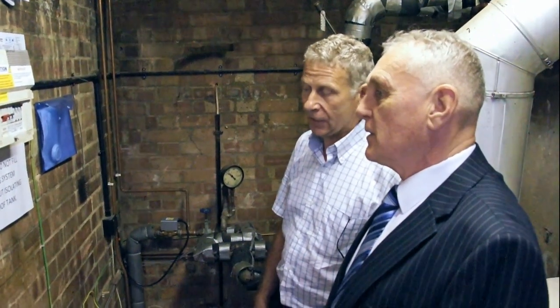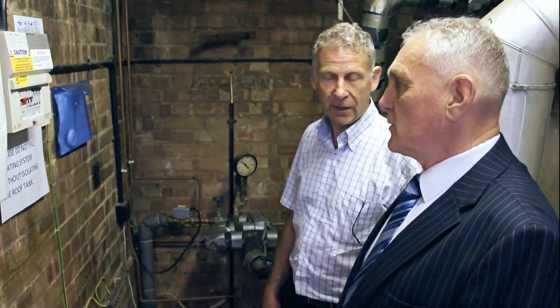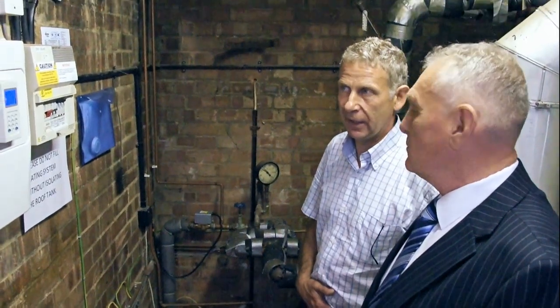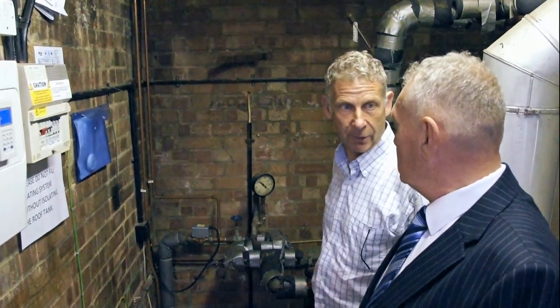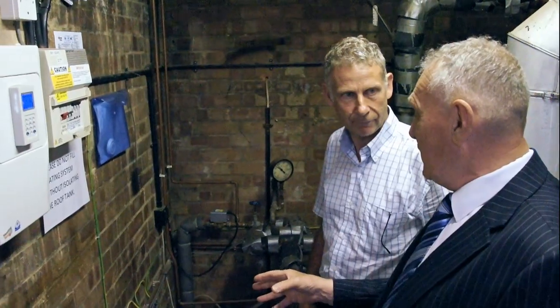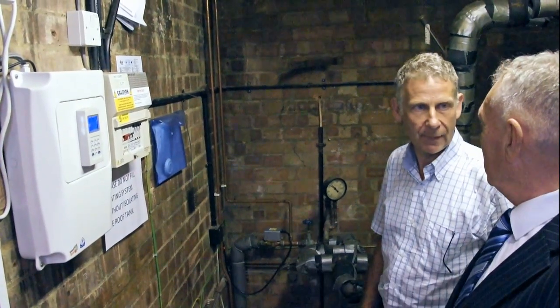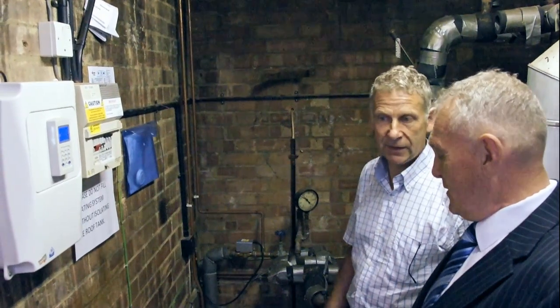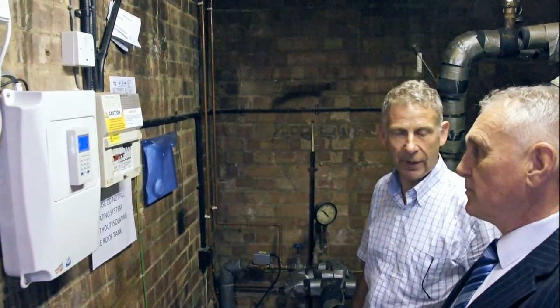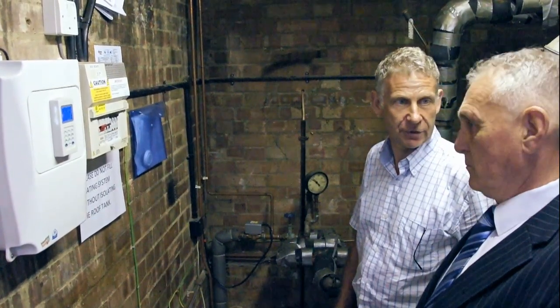The great thing here is that it's a very basic boiler, a very basic system, and it does work with the basic system. It was the best system we could put in here, working with just a single pipe system as we've got in the building, and we're still able to make it all work. You've got a single pipe system, which is probably the most inefficient heating system you could possibly have, and we're controlling that well. We've got a mixture of a wired solution — valves and pumps — but also wireless as well, depending on what we can get into different parts of the building. And going back to it being a listed building, to actually replace the heating system in this building would be a huge job. So this is a way of producing controls as a cost-effective solution for the client.